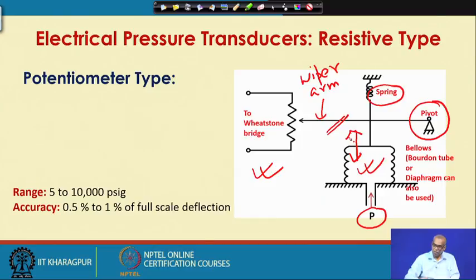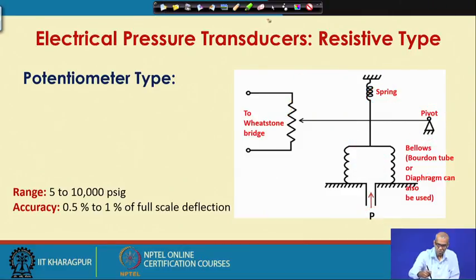As there is deflection, the wiper arm will change the location here. As it does, there will be a voltage output from the Wheatstone bridge. So, initially you get a null point, and then when you apply pressure, the balance will be destroyed because the wiper arm has changed the position. So, the output voltage is a measure of the pressure that you are applying inside the bellows. So, this way you can convert the bellows to a resistive type electrical pressure transducer. The typical range is 5 to 10,000 PSIG, and the accuracy is 0.5% to 1% of full scale deflection.